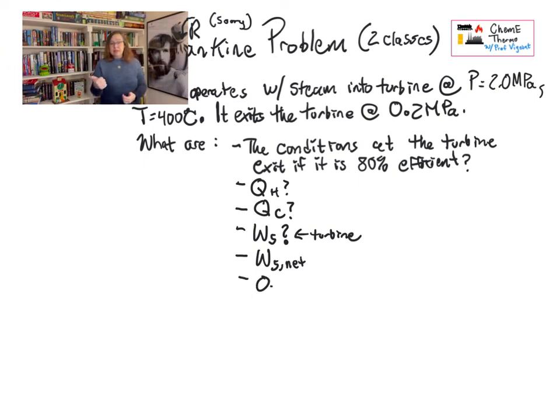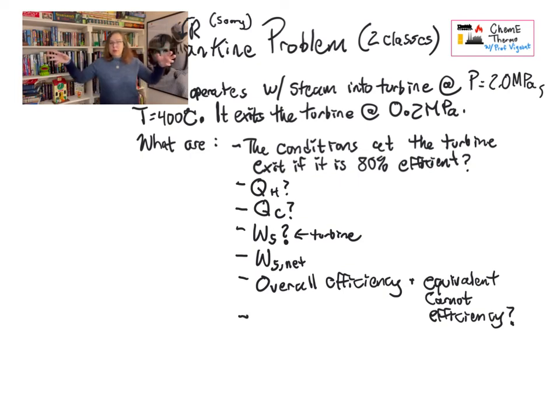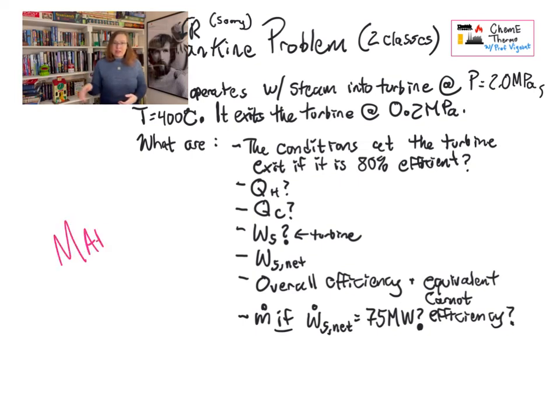What else do we want to know? We want to know QH, that's the heat coming in. QC, the heat that leaves. WS from the turbine. WS net, so that's the turbine and then subtracting off the pump. Because part of the work the turbine is doing is actually powering the pump that keeps the system going. And then what is the overall efficiency of this at turning QH into WS net? And what would be the efficiency of an equivalent Carnot cycle? Remember, you don't have to work everything out about the Carnot cycle. You can use the temperatures to figure out what the efficiency of an equivalent Carnot cycle would be. So you can work that out in one equation at the end. And then finally, what is MDOT? What is our necessary steam flow rate if we want to generate 75 megawatts from this power plant?